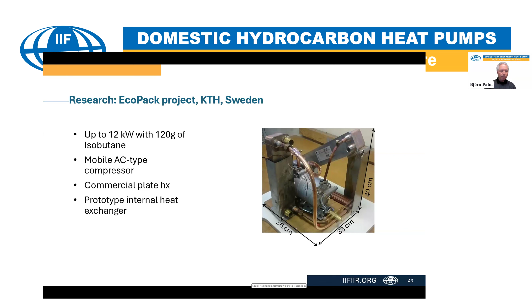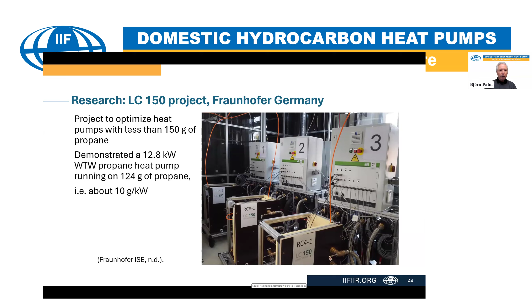At Fraunhofer, they have a similar but much larger research project going on, or actually already finished, LC150. The goal here was to optimize heat pumps with less than 150 gram of propane, and the solution with the low charge, which they demonstrated, was that they could get 12.8 kilowatts out of a water-to-water heat pump with a charge of just 124 gram of propane. So about 10 gram per kilowatt. So more or less the same as we got at KTH.